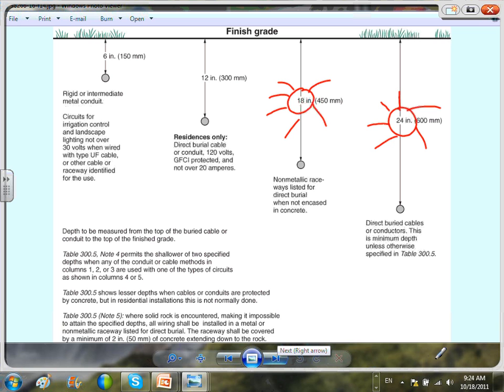Residential only for 120 volt, 20 amp, GFCI protected in residential. Look at the restriction on that one. If that's your situation, you can go 12 inches, direct buried cable, UF direct buried cable. That's how they can get away, between a garage and a house, pulling a UF cable with one foot. Yes?